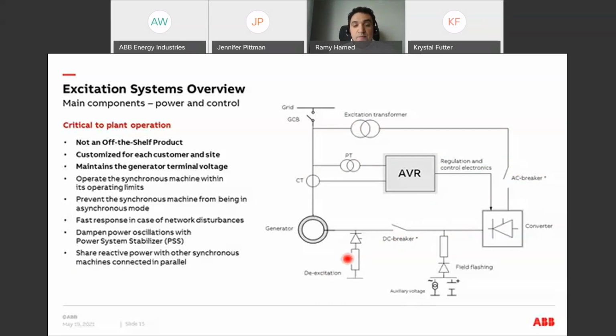And as we explained before, one of the main functions of the excitation system is to do the automatic voltage regulation. And so the control electronics here of the excitation system is always measuring the voltage and the current of the generator. And based on these measurements, it will control the thyristor operation to provide more or less current to the rotor. We have as well the field flashing circuit, which is used to build up the generator voltage in the start sequence of the operation. And finally, we have the de-excitation circuit, which is used to dissipate the energy stored in the rotor in case of a system trip. And so we can see that the excitation system is not an off-the-shelf product, and that many components of the excitation system need to be customized based on different units.